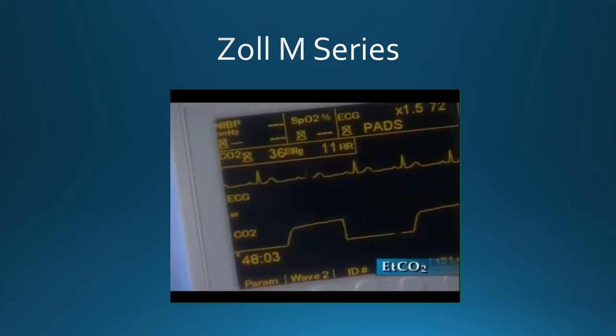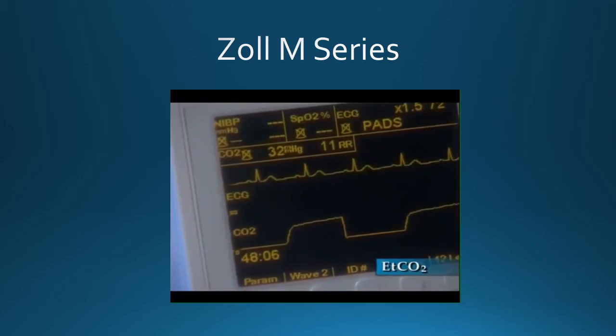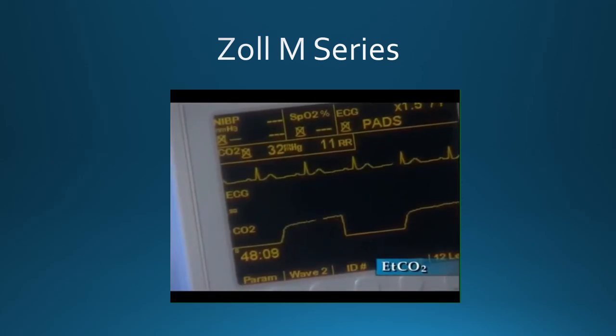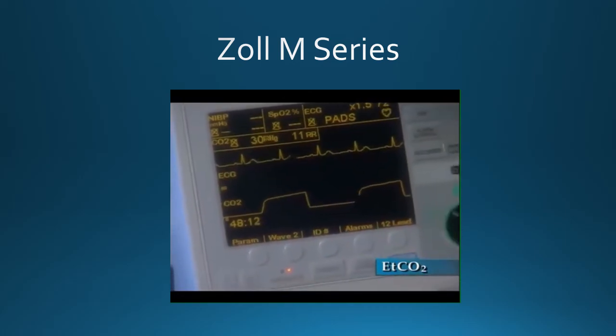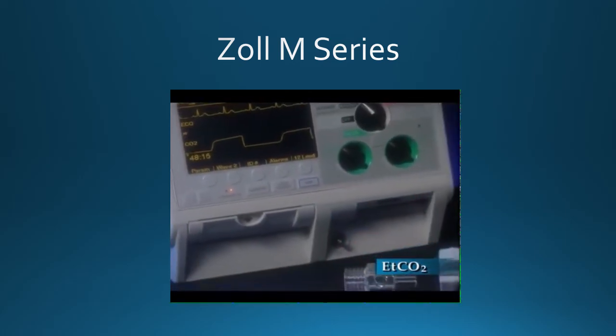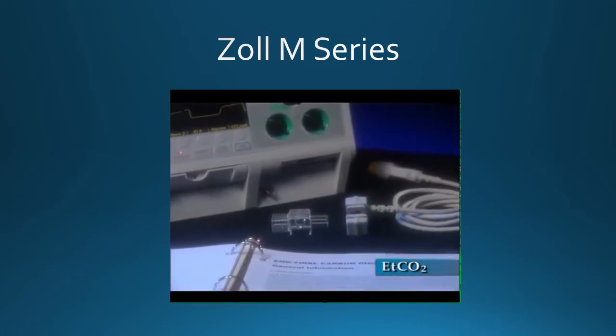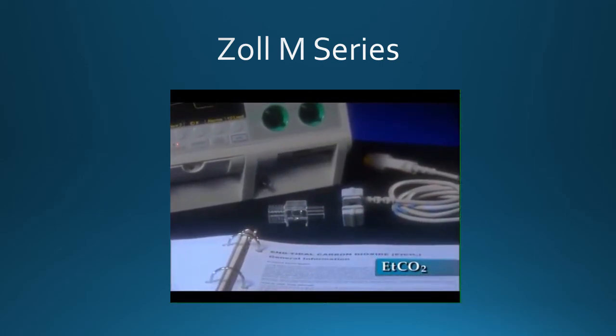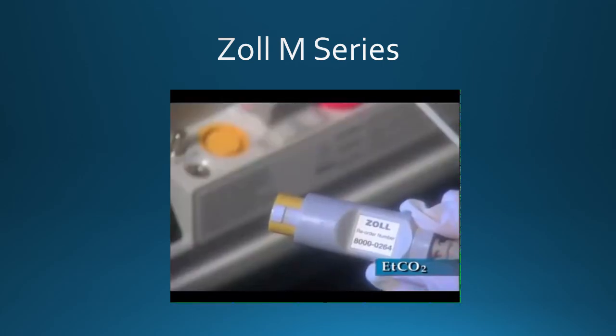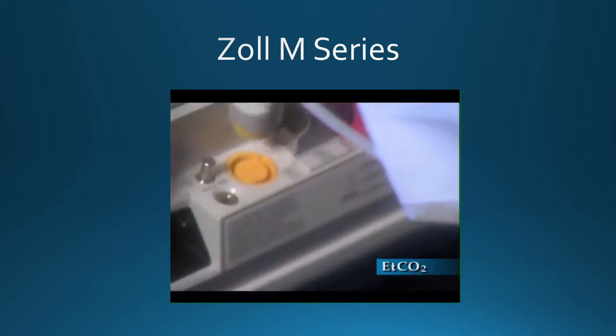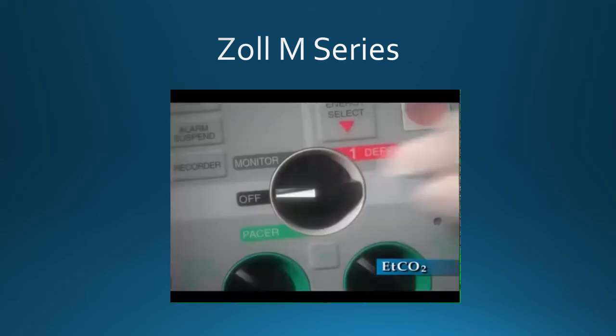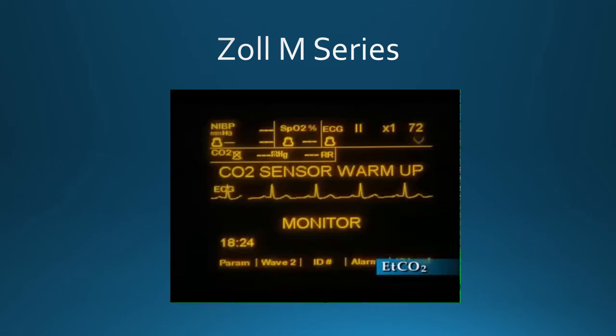Your M-Series may be equipped with a Novametrix end-tidal CO2 monitoring option, which continuously measures carbon dioxide and respiratory rate using a unique mainstream solid-state sensor called a capnostat. Please review the end-tidal CO2 Operator's Guide insert for detailed instruction. Attach the capnostat CO2 sensor cable to the CO2 connector at the rear of the M-Series. Turn the selector switch to monitor. Wait for the CO2 sensor to warm up. This will take approximately 60 seconds or less. The message CO2 sensor warm up will disappear when the capnostat is ready for use.